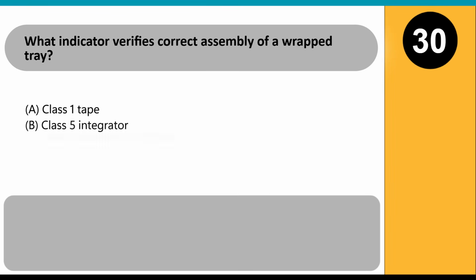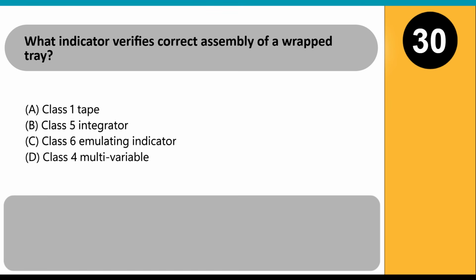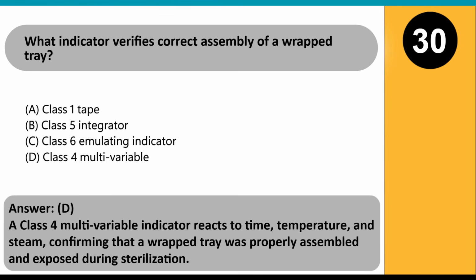What indicator verifies correct assembly of a wrapped tray? A. Class 1 tape. B. Class 5 integrator. C. Class 6 emulating indicator. D. Class 4 multivariable. Answer: D. A Class 4 multivariable indicator reacts to time, temperature, and steam, confirming that a wrapped tray was properly assembled and exposed during sterilization.